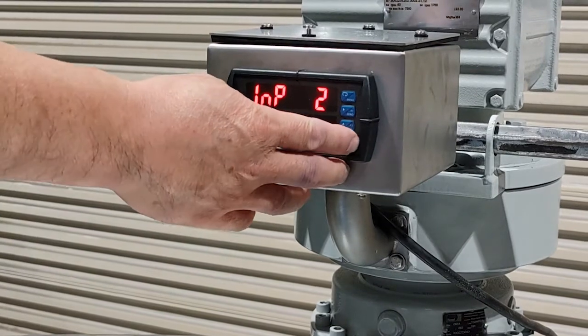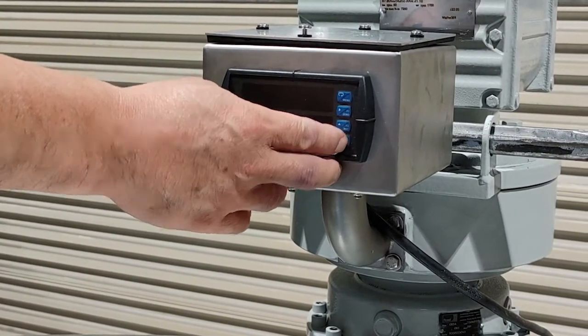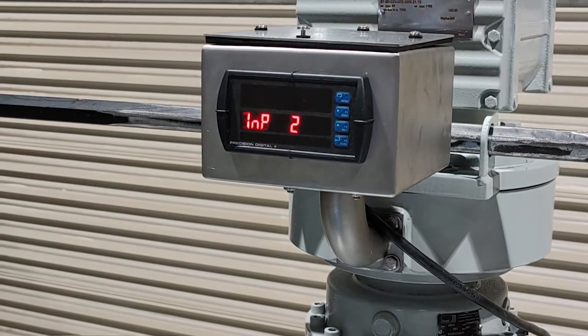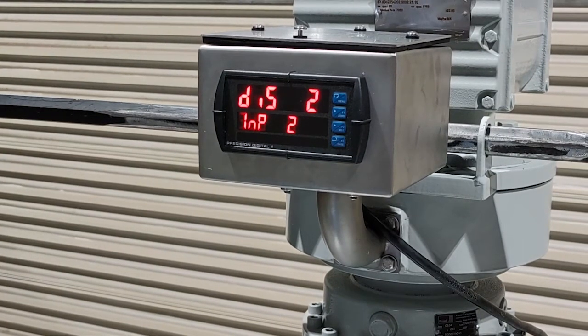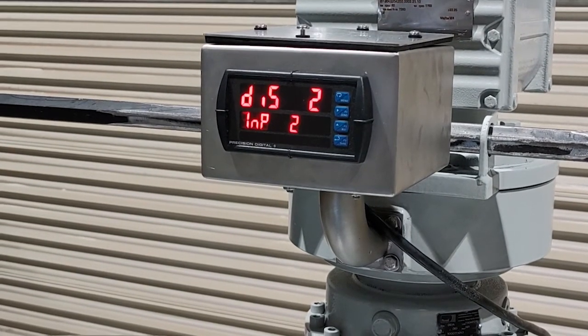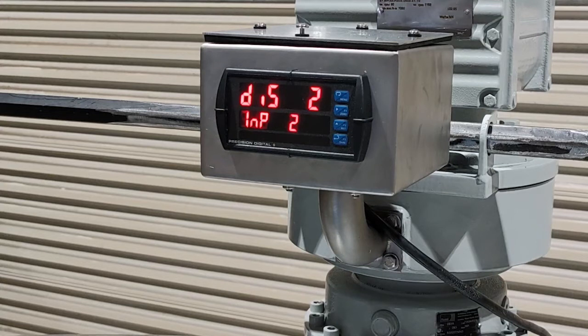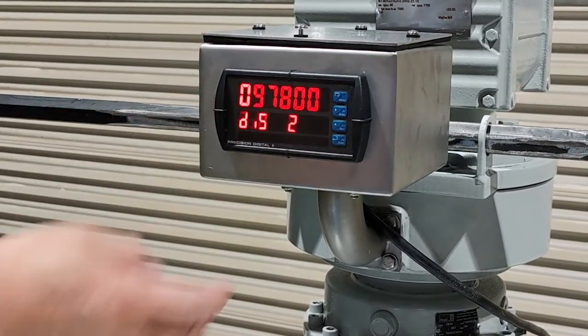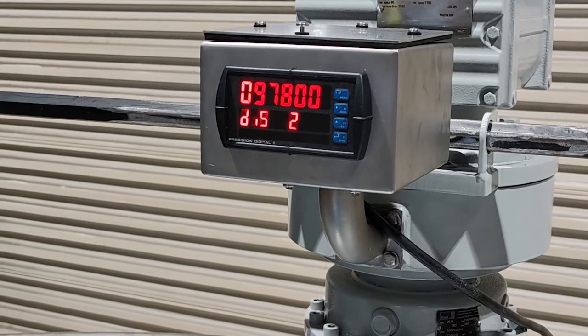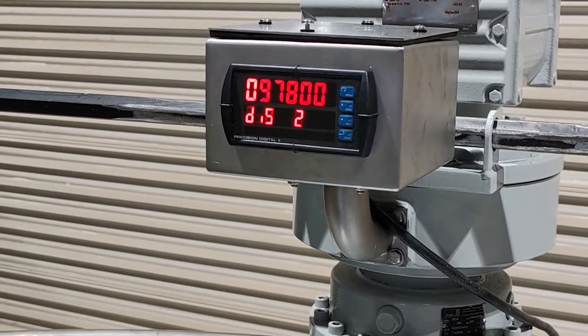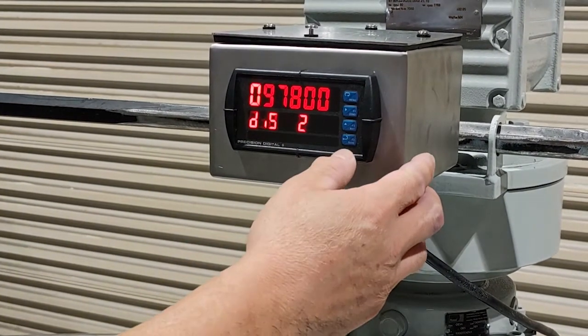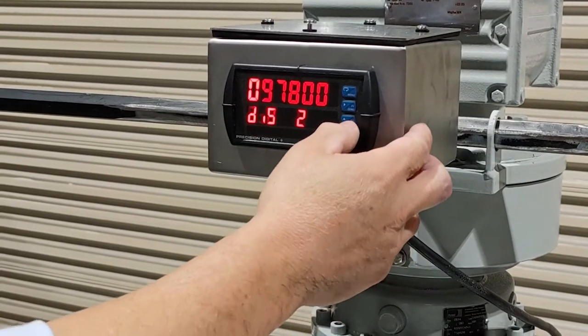Press the Enter button to tell the program to collect the signal from the load cell. The screen will again blink 3 times to show that the signal is being collected, and it will display DIS2 when the signal is stored. You may now release the weight to rest back on the floor. Press the Enter button to enter the value you want the screen to display when it reads the stored signal. Refer to the calculation sheet in your O&M manual for the calibration torque display value.